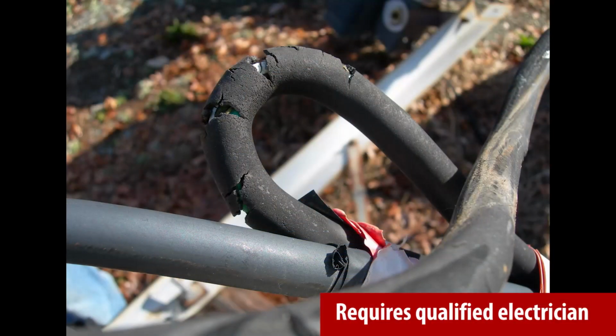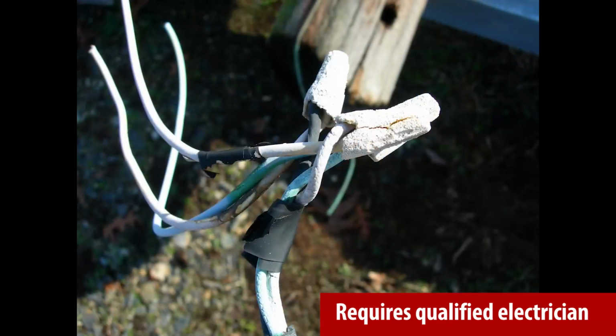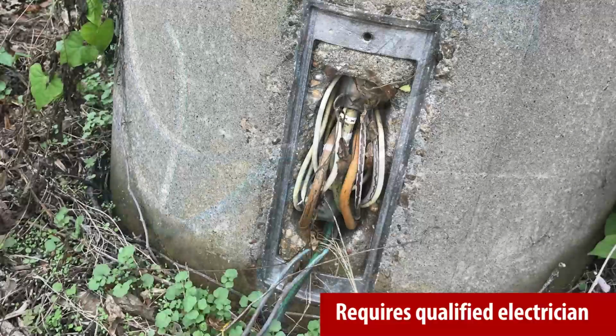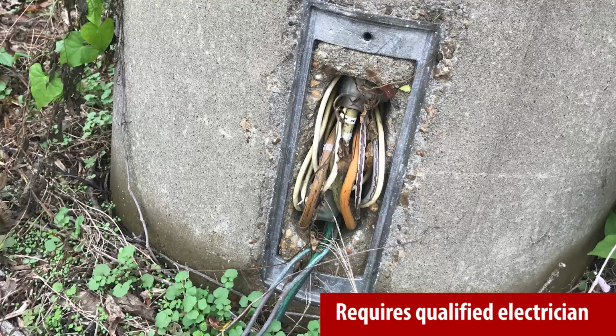As you move along with your inspection, you always want to visually inspect your wiring. Look for cracked or damaged insulation and also discoloring. Discoloring is caused by heat, which usually leads to a loose or defective termination, which could be a termination on a circuit breaker, in a wire nut, Polaris block, etc.